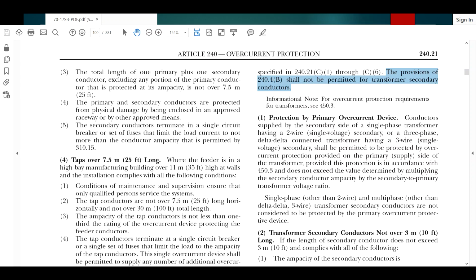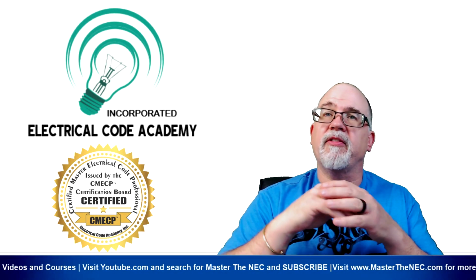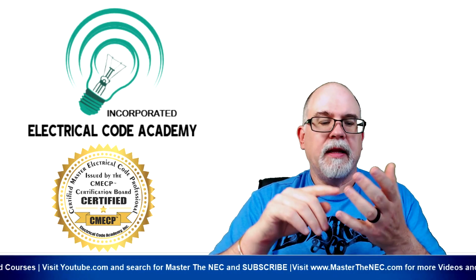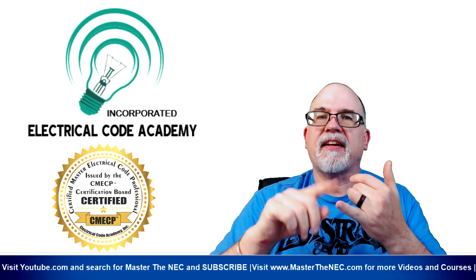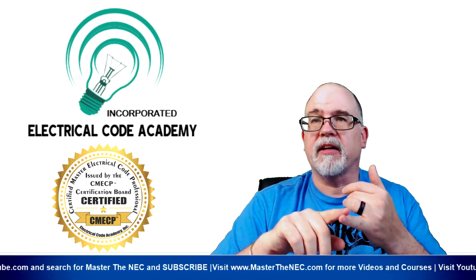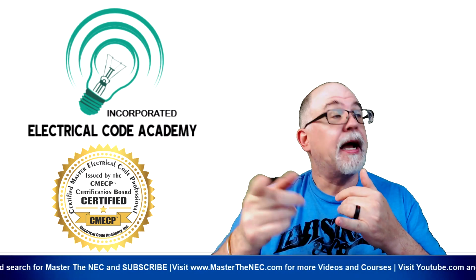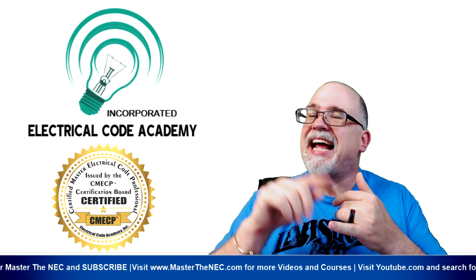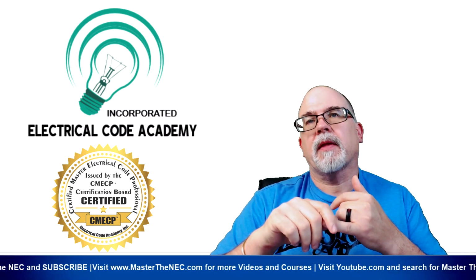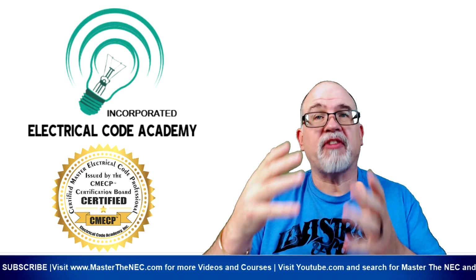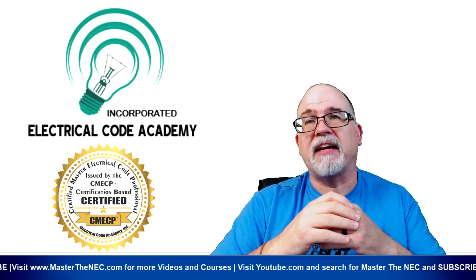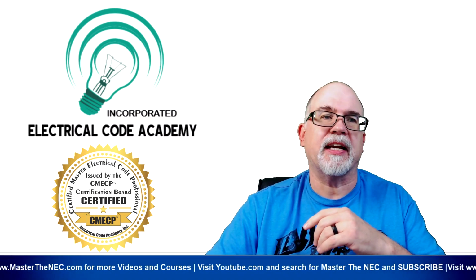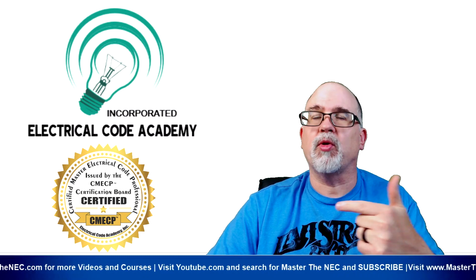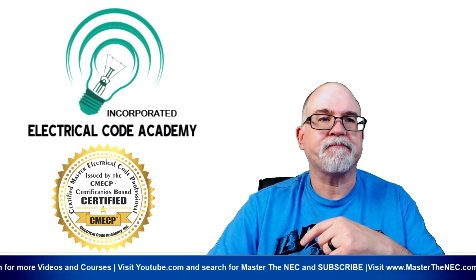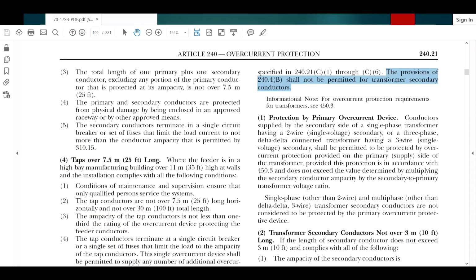Okay? What does that mean? Well, if you remember in previous parts of this episode, I cannot use the next size up rule on the secondary conductors. I can do it on the primary, I can do it on other aspects of the code, but I cannot do it here because I have to size them full size based on whatever the device is that I terminated into. And you're going to see that rule here in a second. So again, I can't use the next size up rule that's found in 240.4b. Okay? All right, so that's the rule that we have to remember for that.